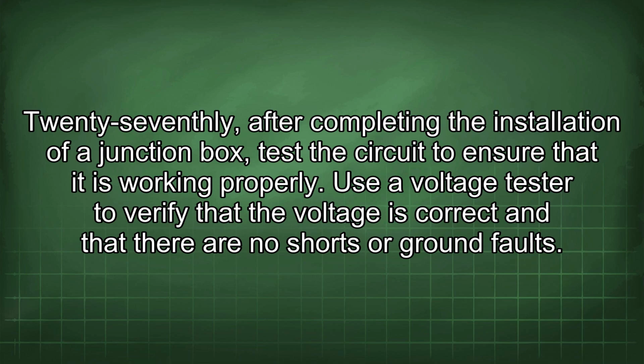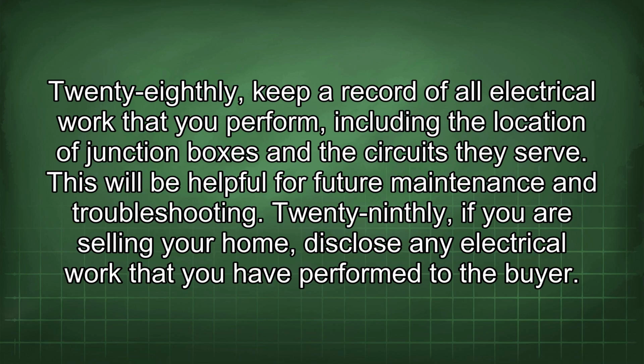27thly, after completing the installation of a junction box, test the circuit to ensure that it is working properly. Use a voltage tester to verify that the voltage is correct and that there are no shorts or ground faults. 28thly, keep a record of all electrical work that you perform, including the location of junction boxes and the circuits they serve.